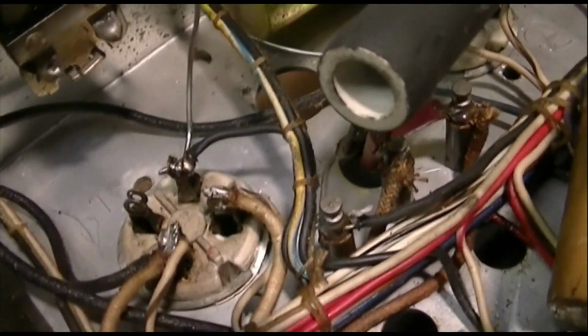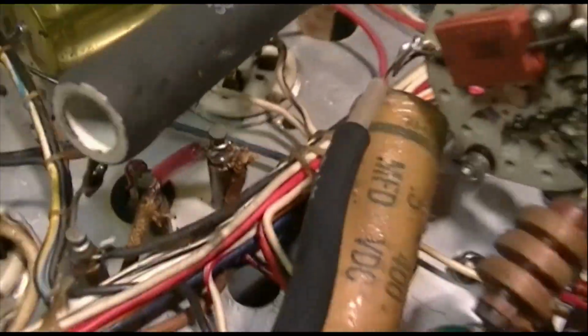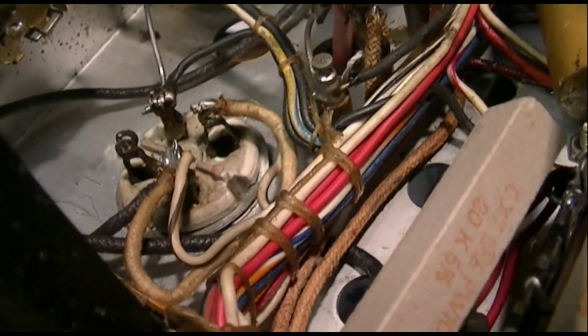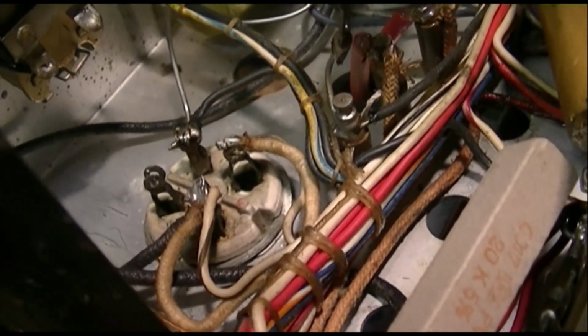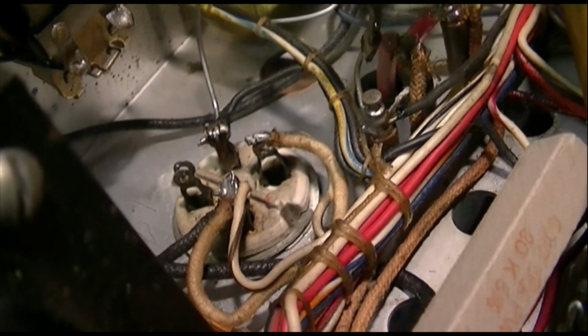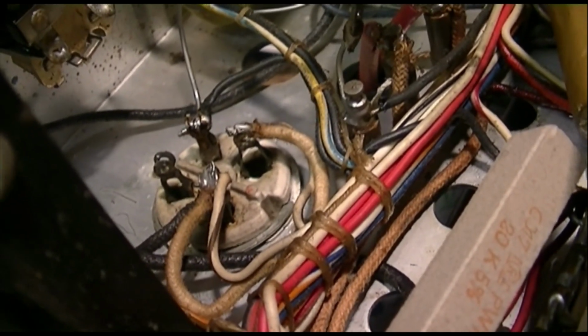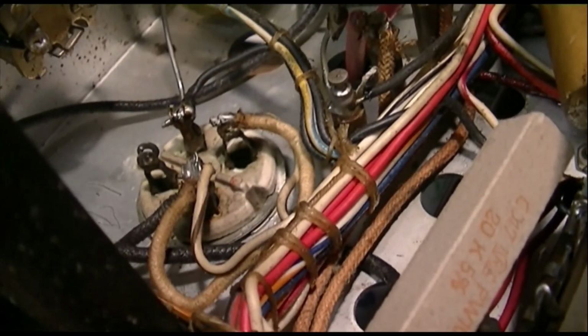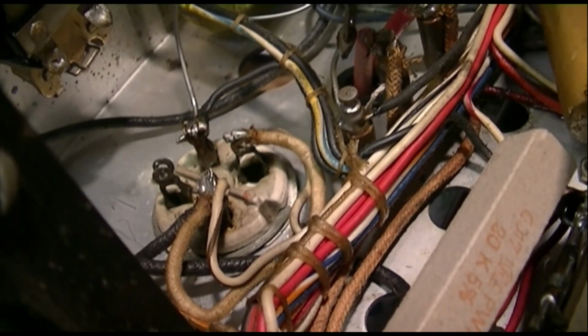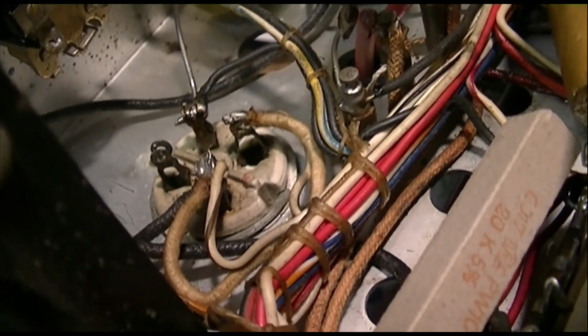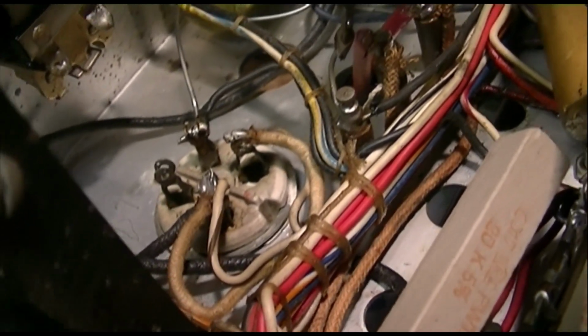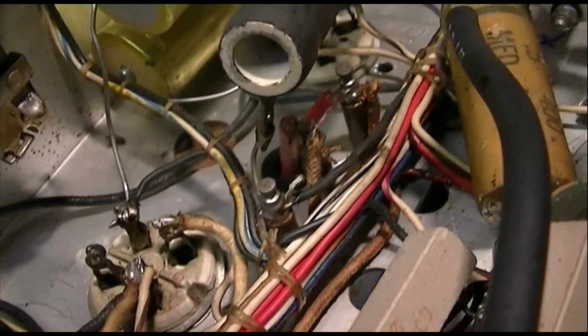So the cheap insurance is to keep these things squeaky clean so you don't develop an arc path. You get an arc path because you've got dirt, and the dirt absorbs moisture from the atmosphere, creating a conductive path. With high voltage, like 1,000 volts or more, it can follow that path along where a lower voltage couldn't, and then you've got problems.